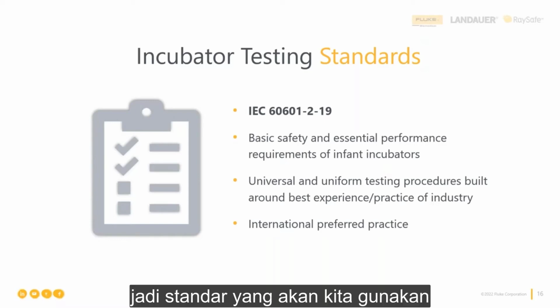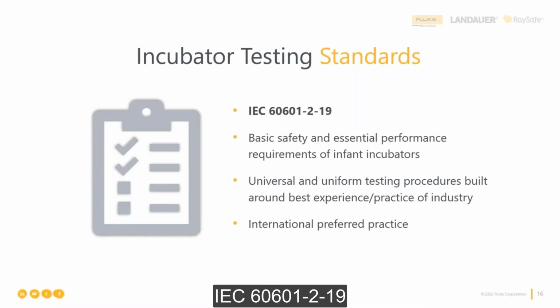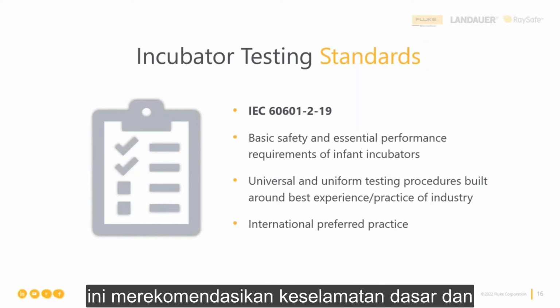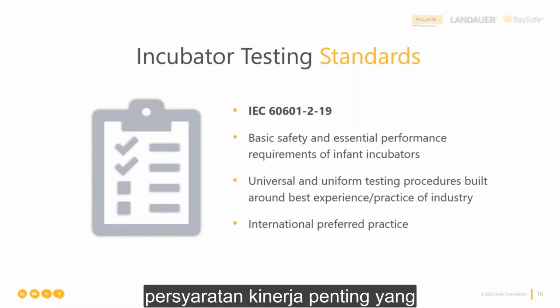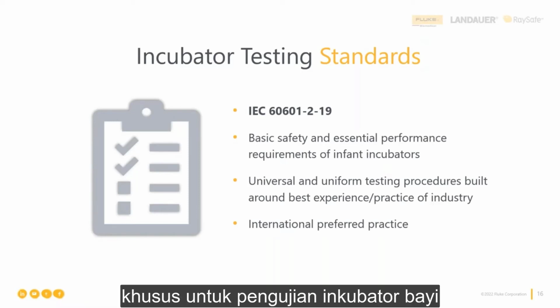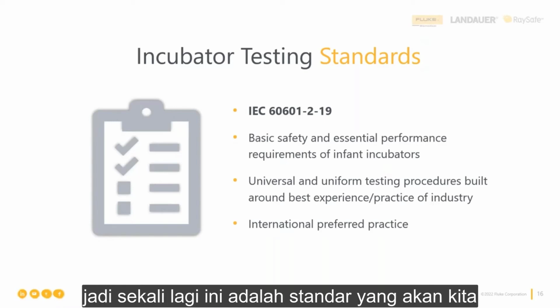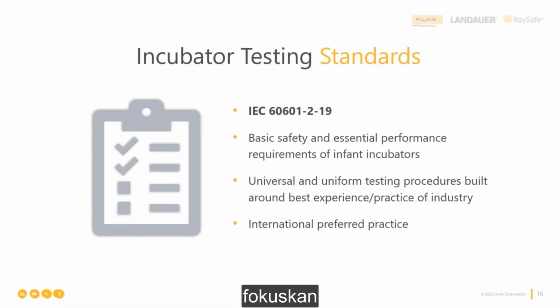So the standard that we're going to focus on is the IEC 60601-2-19 standard. This recommends basic safety and essential performance requirements that are specific to infant incubator testing. So again, this is the standard we'll be focusing on today.